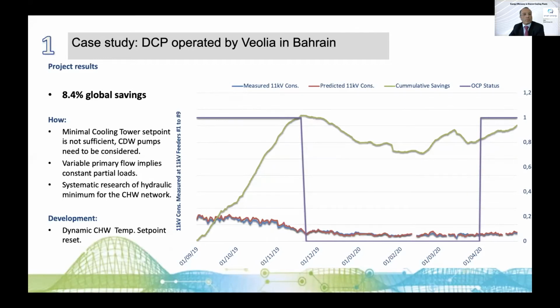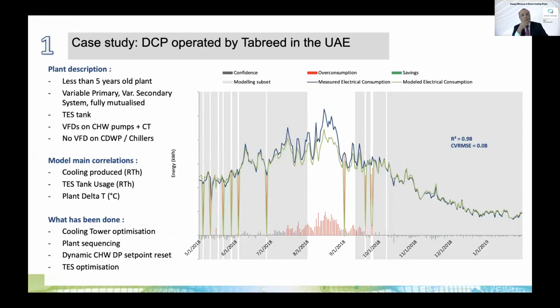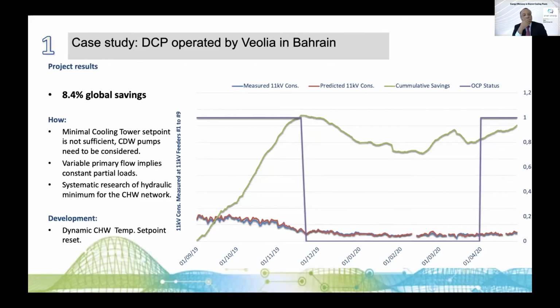I mean, it's leading to overconsumption essentially. And so the system went back on in April, and the savings you can see are increasing afterwards. We are currently working on the last development, which is the dynamic chilled water temperature set point reset.